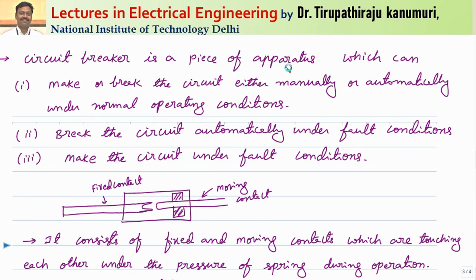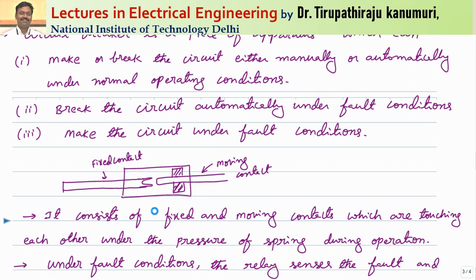Coming to the circuit breaker: a circuit breaker is a piece of apparatus which can make or break the circuit either manually or automatically under normal operating conditions as well as under fault conditions. It should automatically detect the fault and isolate the circuit under fault conditions, and it should also be able to make the circuit under fault conditions. Generally, in order to maintain the continuity of supply in power systems, we go for automatic reclosers. Whenever your circuit breaker opens due to some fault, 80 percent of faults that happen in transmission lines are transient faults — meaning they will die out within a fraction of a second. So there is no need to go and check them; we can reclose our circuit breaker automatically. But the remaining 20 percent of faults may be permanent faults, meaning when you are closing your circuit breaker you are closing under fault conditions, so your circuit breaker should be able to withstand that high value of current when the circuit is closed, and similarly it should be able to open under high values of fault currents.